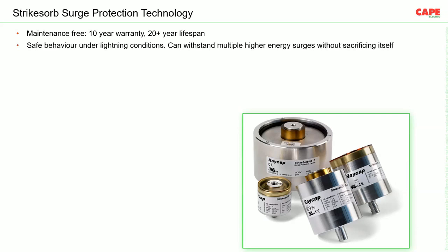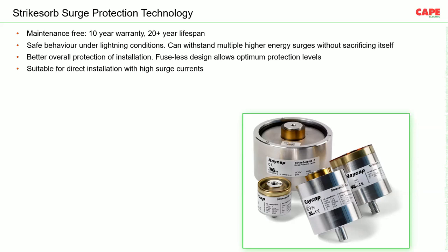Safe behavior under lightning condition. The SPD can withstand multiple higher energy surges without sacrificing itself. This we are going to discuss in a further slide; there are test details in the next slide. Better overall protection: the fuseless design allows optimum protection level. Up to a certain ampere rating, these SPDs don't need backup protection, so that allows a very low voltage protection level. They are suitable for direct installation with high surge current, for places where surges are very common and very frequent.